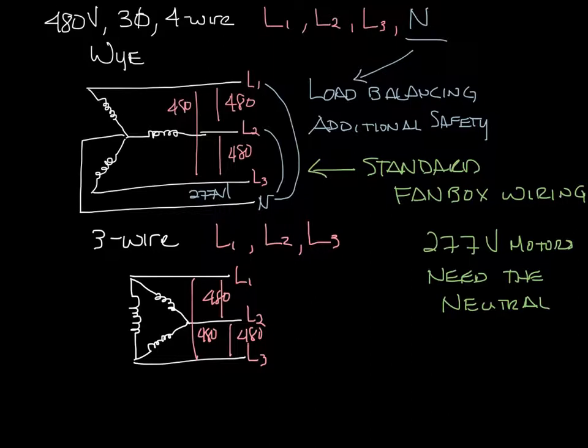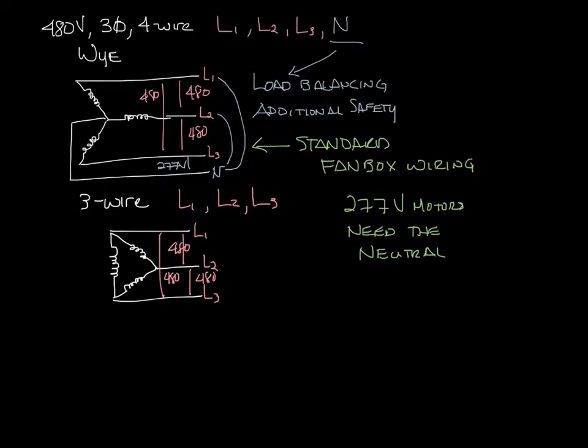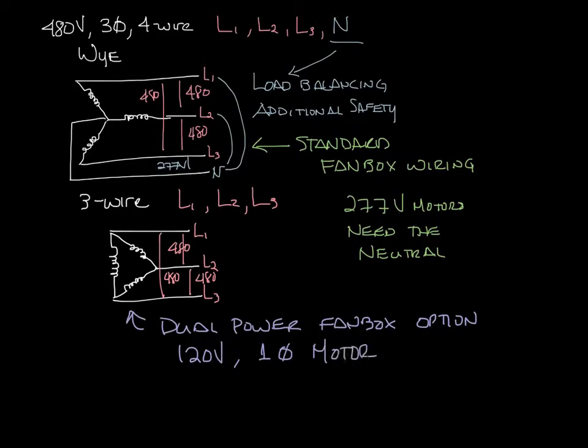Now let's say you wanted a 277-volt motor and a 480-volt electric heater on a 3-wire system. Make a little room. So what you get here is a dual power fan box. You would have line voltage for a 120-volt single-phase motor. And then you would have 480 volts for your electric heaters.